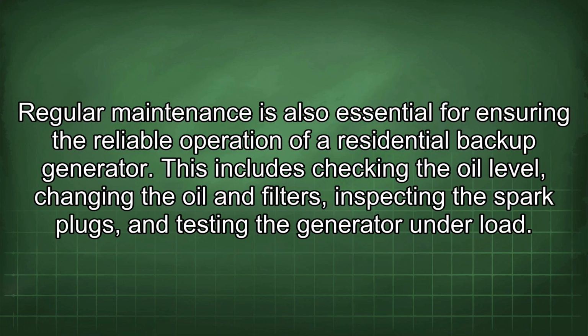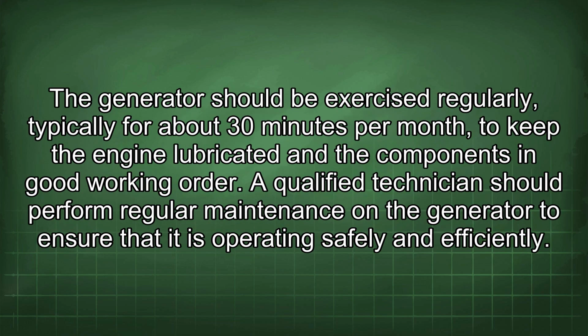Regular maintenance is also essential for ensuring the reliable operation of a residential backup generator. This includes checking the oil level, changing the oil and filters, inspecting the spark plugs, and testing the generator under load. The generator should be exercised regularly, typically for about 30 minutes per month, to keep the engine lubricated and the components in good working order. A qualified technician should perform regular maintenance on the generator to ensure that it is operating safely and efficiently.